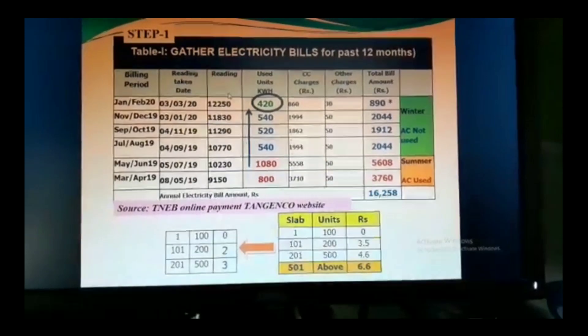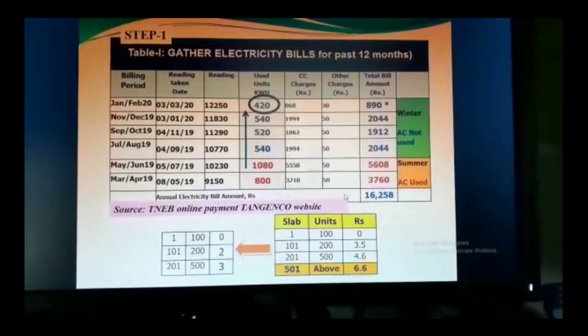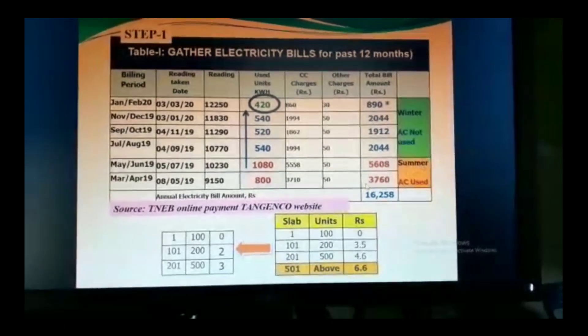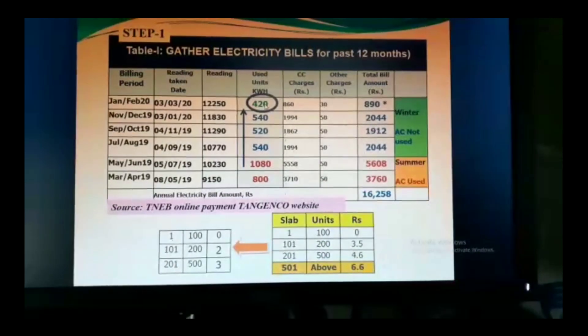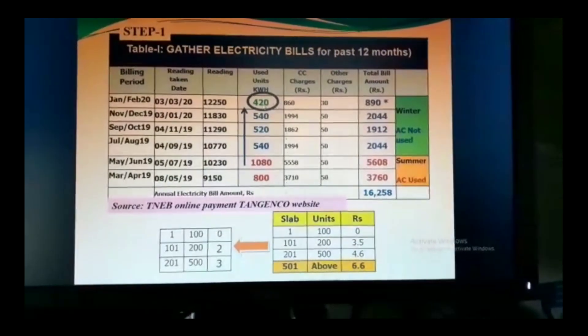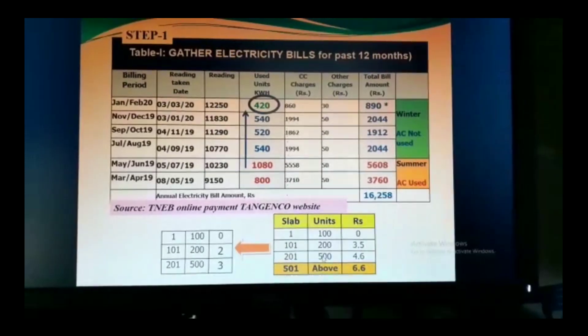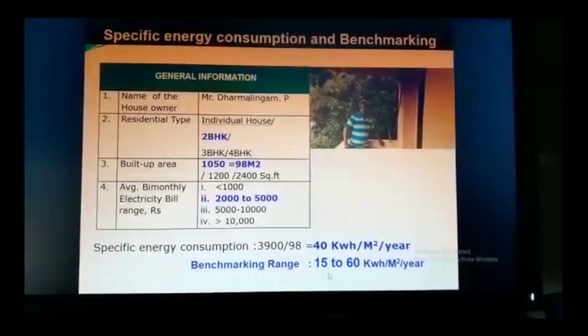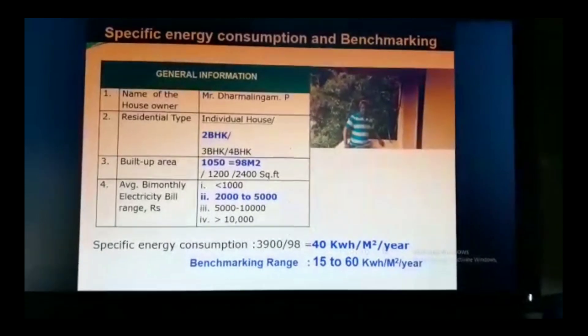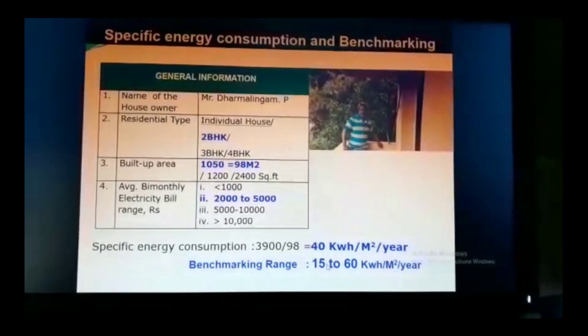For step one, you can collect electricity bills from the TNEB website. This data is for a two-BHK, 1,000 square feet house. During summer they spent 5,600 rupees, dropping below 1,000 rupees in winter — January and February show the lowest consumption, as the household moved from the above-500-unit slab rate to below 500 units. Working out the specific energy consumption gives 40 kWh per square meter per year, but the benchmark is as low as 15, so there is a vast gap and the objective is to reduce it by at least 20–25%.